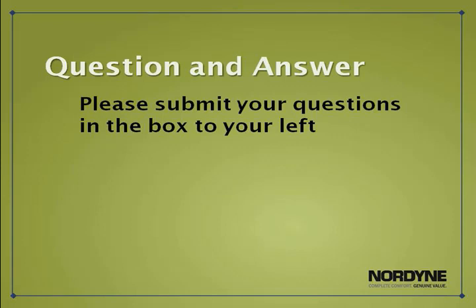Another question from Randy with American Air Systems. What is the capacity range between C1 and C5, and how many speeds does the air handler use? C1 and C5, it's anywhere from 40 to 118. I don't have the specific numbers in front of me, but it's a minimum of 40% capacity up to 118, similar to the IQ Drive 23 SEER. And air handler speeds or gas furnace speeds will be 2 speeds. You'll have a low speed and a high speed.